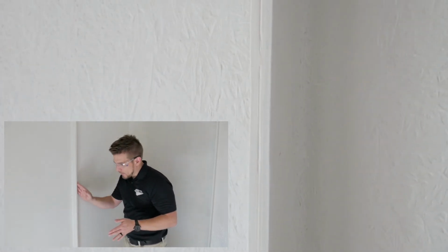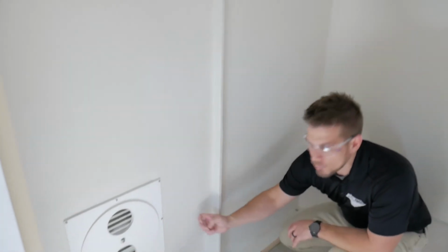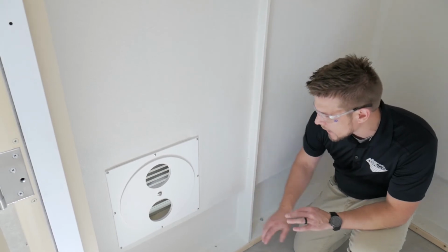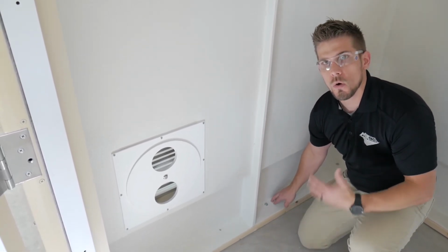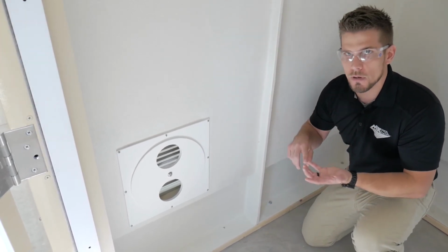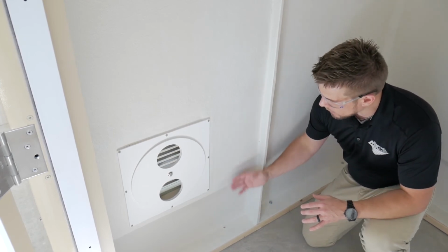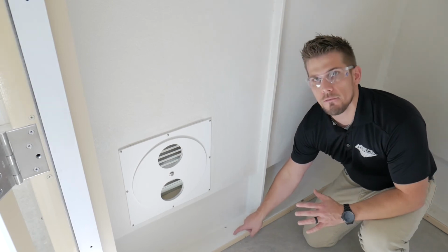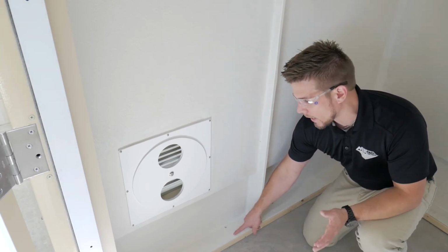If we look down the building here, we'll see that towards the base, we don't have 3 inches of embedded foam, and rather we have 1 inch. And the reason we've done that is to enable access to the mounting holes or bracketry that would hold this building to the concrete pad or the steel base, what have you, in the field. If we were to carry this foam all the way through, we wouldn't have enough of a shoulder for that bolt or anchor, wedge anchor, to land upon.